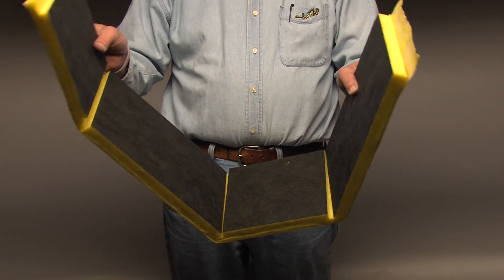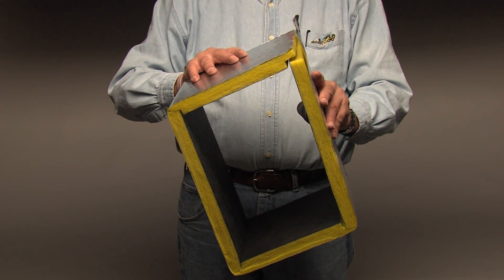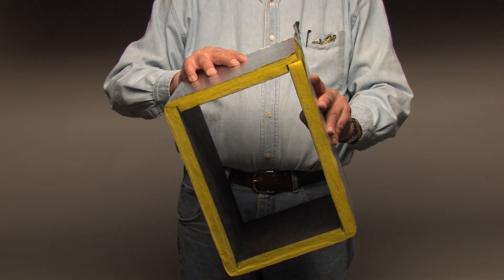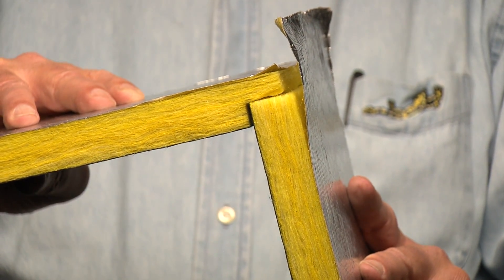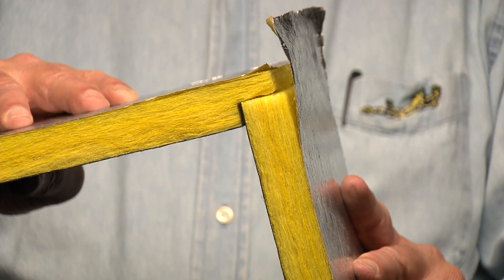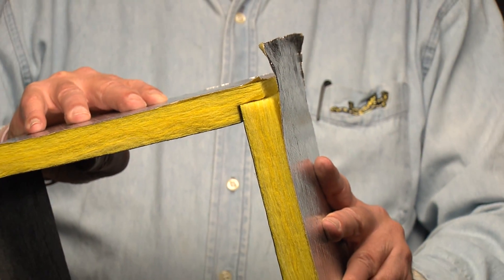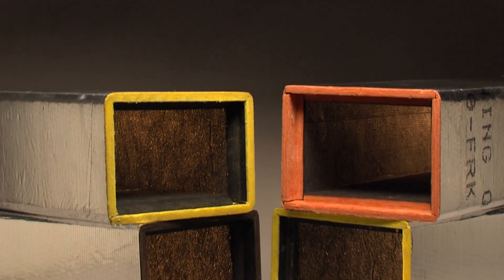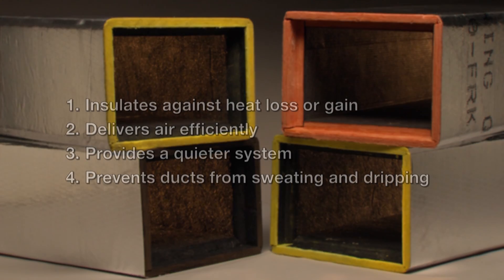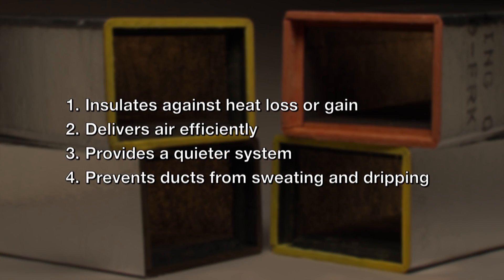Ducts are formed by making grooved cuts in the board and folding it into a duct, sort of like forming sheet metal in a brake. The longitudinal joint, when stapled and taped in place, is like a Pittsburgh joint in sheet metal — it forms an airtight seam and holds the duct together. The finished duct meets the building codes and does four jobs: insulates against heat loss or gain, delivers air efficiently, provides a quieter system because the insulation attenuates noise in the duct work, and prevents ducts from sweating and dripping.